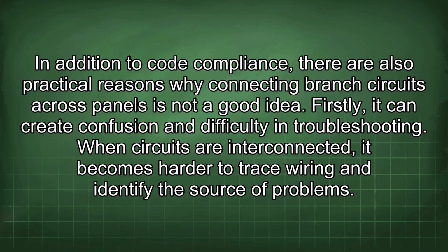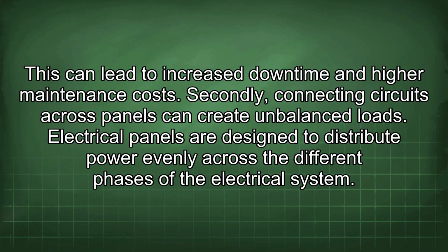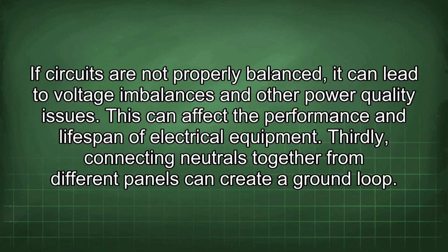In addition to code compliance, there are also practical reasons why connecting branch circuits across panels is not a good idea. Firstly, it can create confusion and difficulty in troubleshooting. When circuits are interconnected, it becomes harder to trace wiring and identify the source of problems. This can lead to increased downtime and higher maintenance costs. Secondly, connecting circuits across panels can create unbalanced loads. Electrical panels are designed to distribute power evenly across the different phases of the electrical system. If circuits are not properly balanced, it can lead to voltage imbalances and other power quality issues. This can affect the performance and lifespan of electrical equipment.